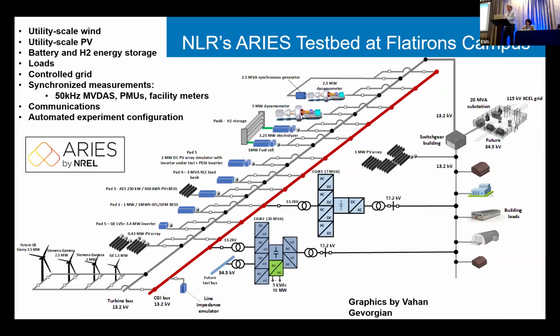Kind of an overall schematic view of the site shows how everything's interconnected. So one of the really big values of our site at Flatirons campus is we have all of these megawatt scale assets distributed across the whole site, and we can interconnect them to each other or to the 2 grid simulators or to the utility. So we've got a 20 MVA substation with 115 kV feed from Xcel. It says 20 MVA. We're limited to 20 MVA of export through that substation, but we can pull up to 50 just because of the interconnection agreement.